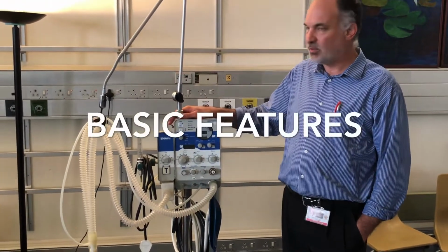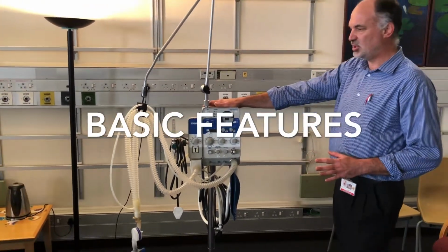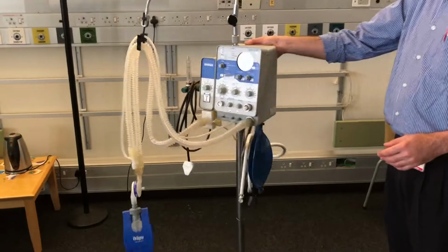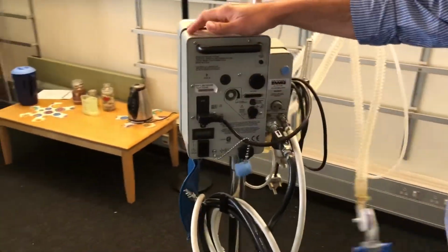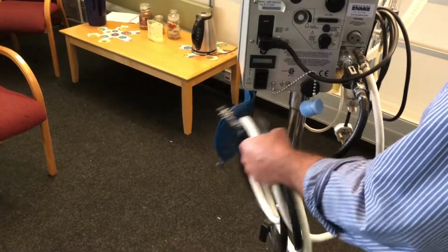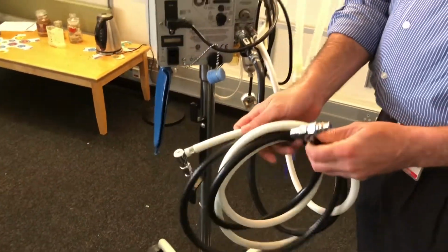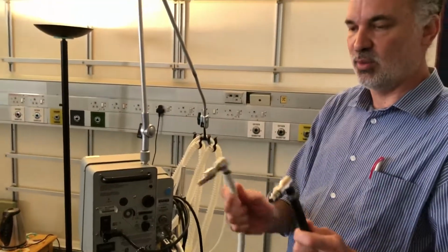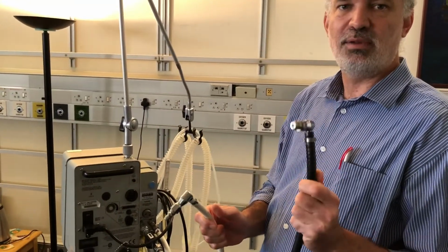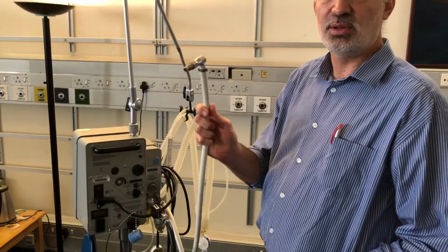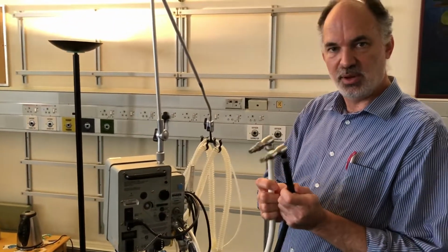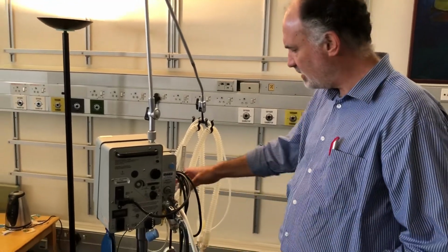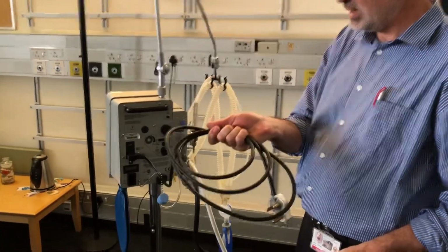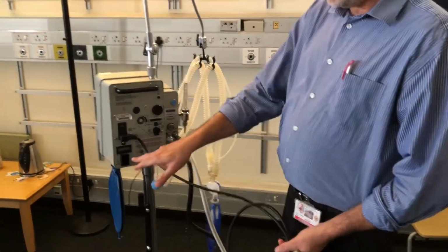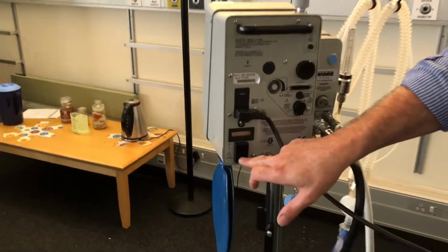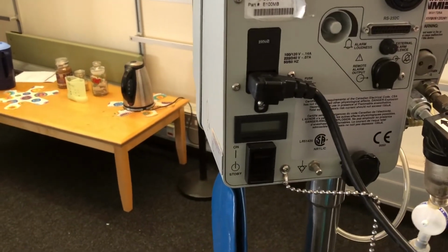So to start off with, I just want to point out a few general features of the machine which make it a little different and that you need to be aware of. The first thing is if we look at the back of the machine, you'll see that this machine needs to be plugged into both air and oxygen. So there are two hoses that need to be connected into the wall, one for oxygen and one for air. Most of our newer ventilators only use an oxygen connector, but these both need to be plugged in. Like other ventilators, we need to plug the electrical supply in to the wall, and we need to switch the ventilator on, and the on switch is at the back of the machine on the bottom left hand side.